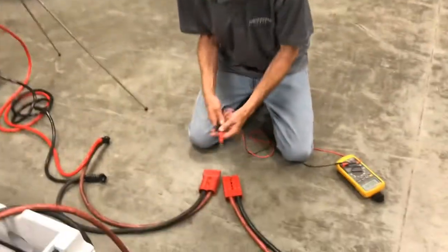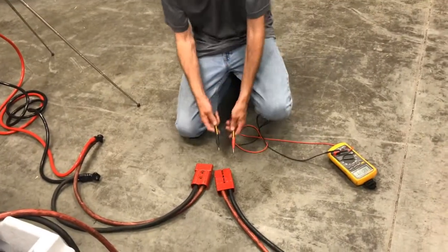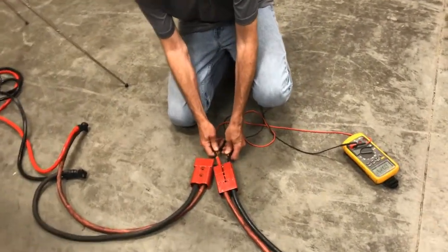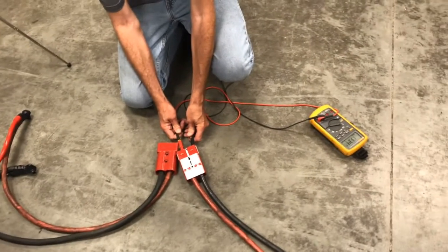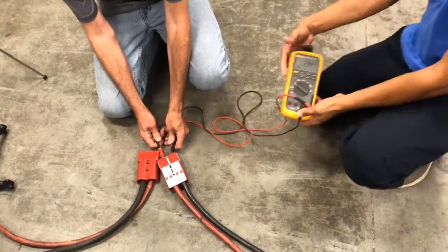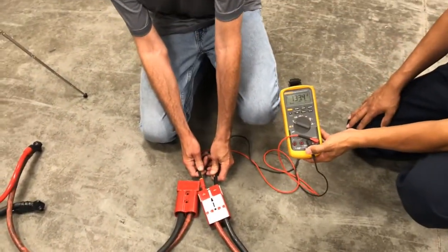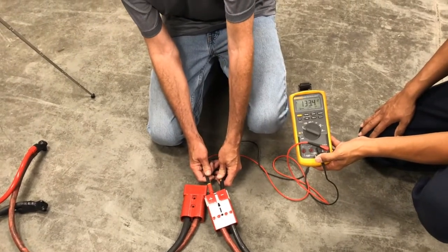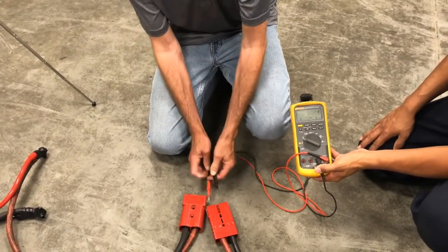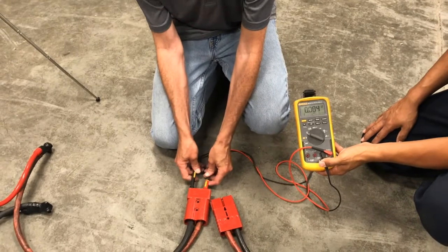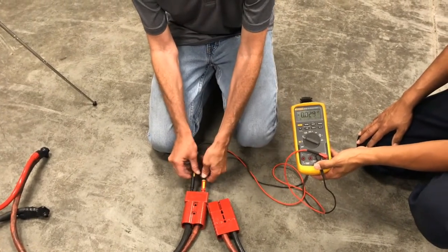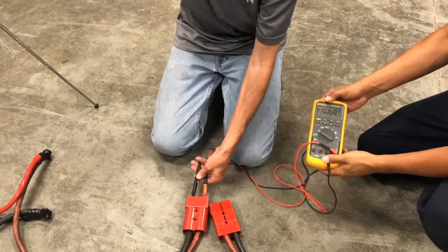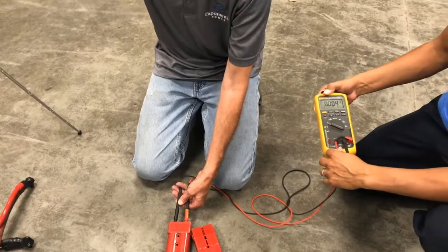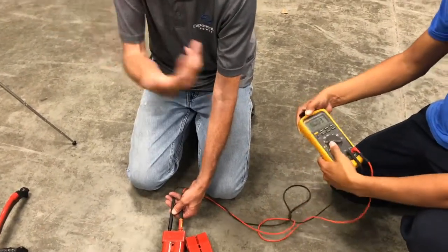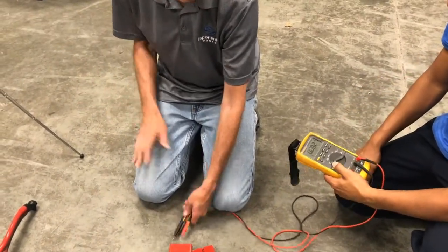So as part of our safety, we always check connectors before we connect an Anderson connector together. So we always measure that we've got the correct polarity on all these connectors before we connect any battery system to any charger, or any load bank, or anything like that. So we'll go in, and on the load bank side right now, I don't have any voltage because the load bank isn't a source of power. The load bank only consumes power.